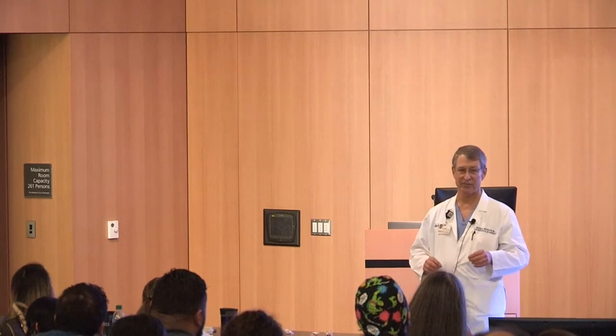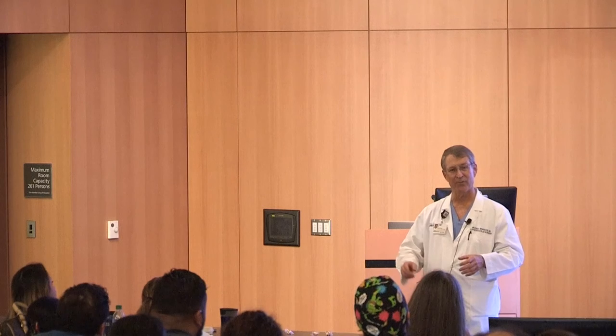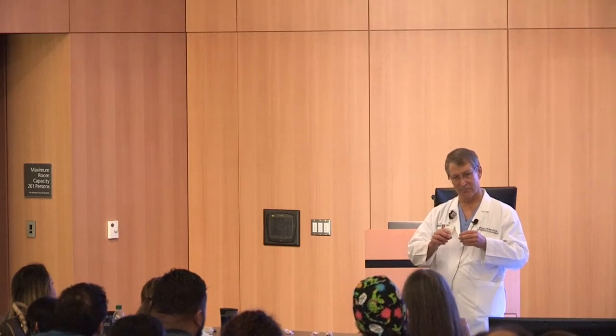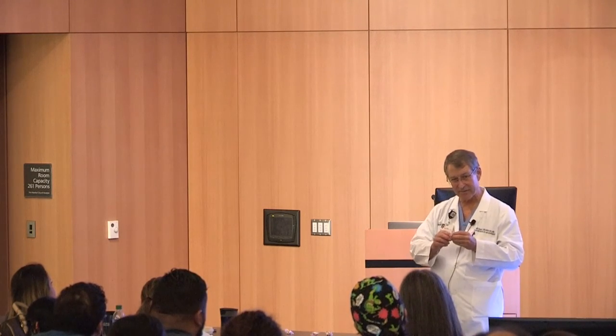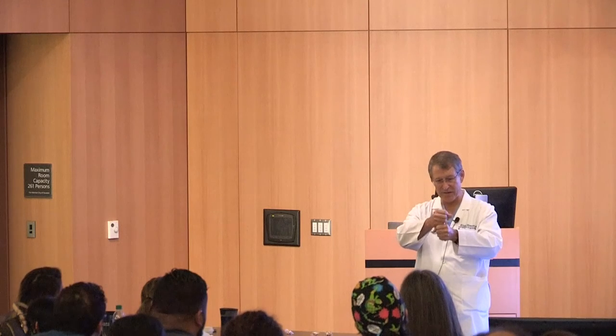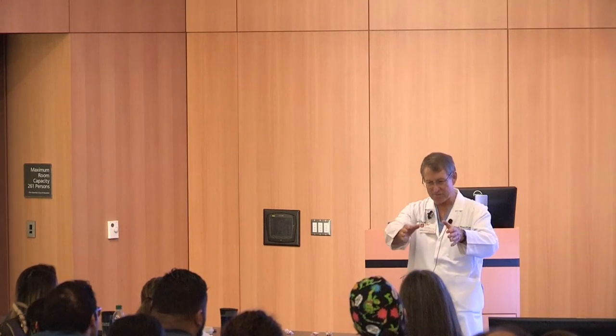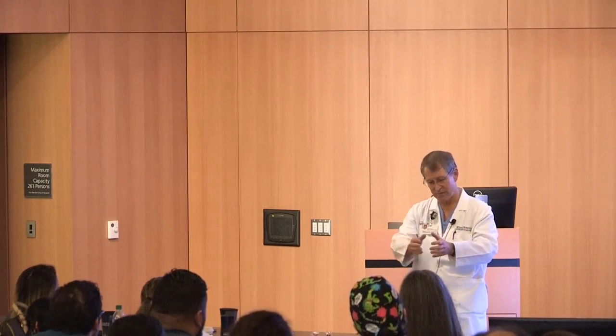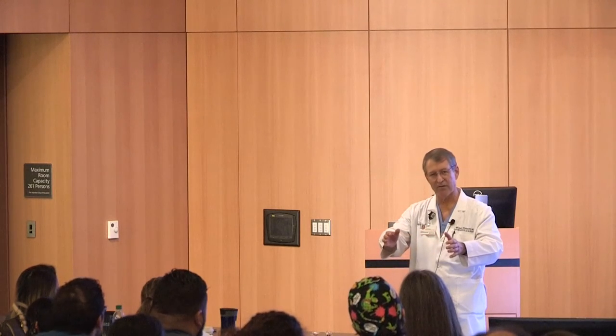For the Evolut, it's a little different. We blow up the balloon with a valve, but then with this valve, being nitinol, which has a memory like a spring, instead of crimping it onto a balloon, we load it inside a sheath, and as we pull the sheath back, it flowers into position slowly. So we're turning a wheel, pulling the sheath back, and watching the valve flower into position.